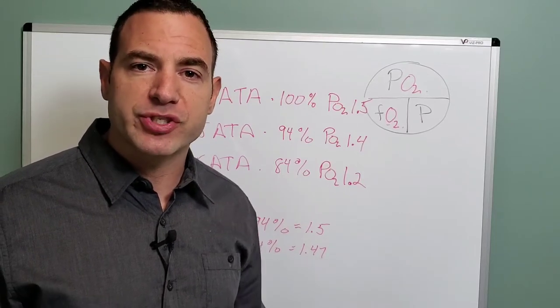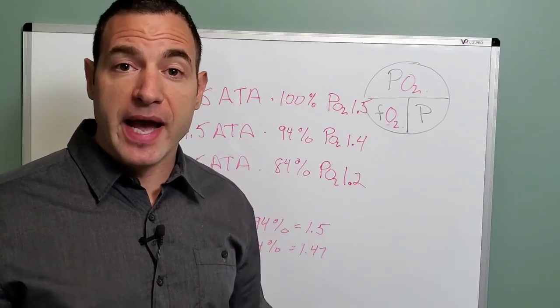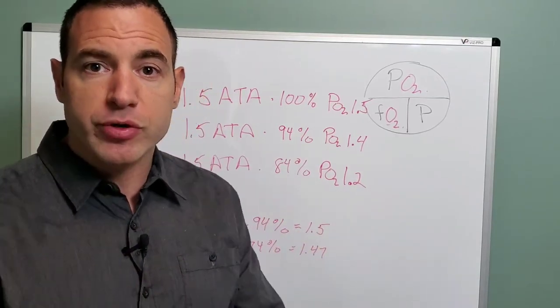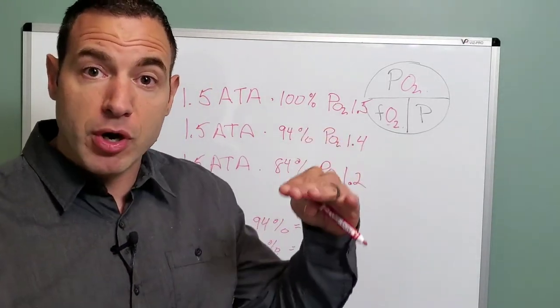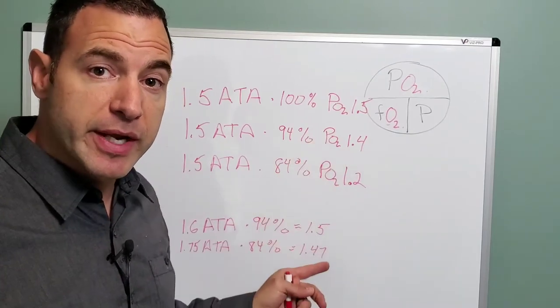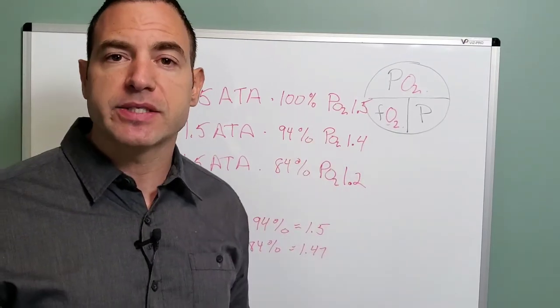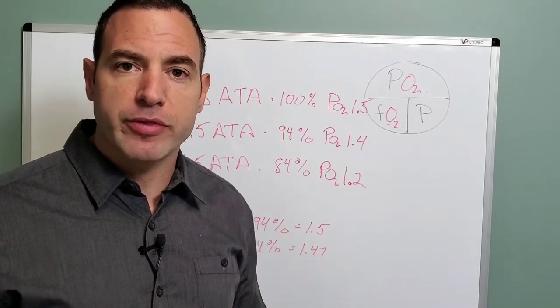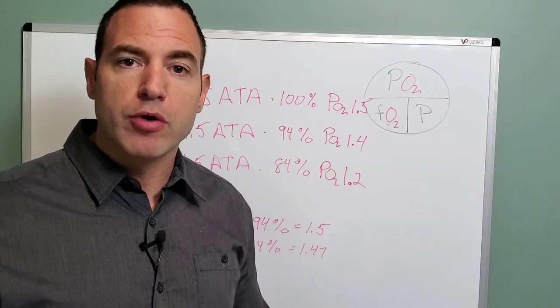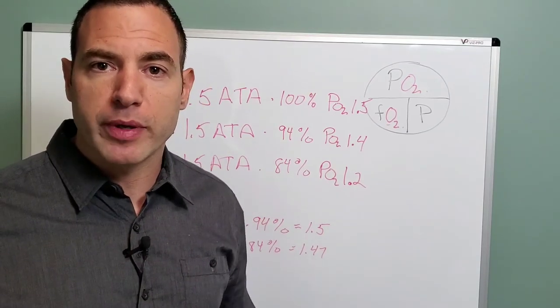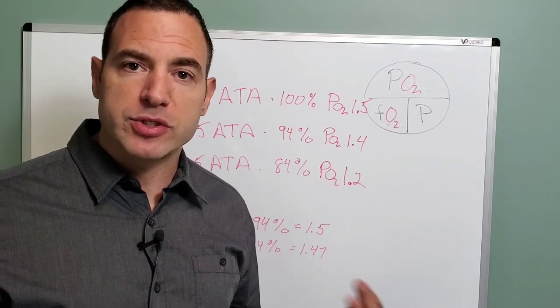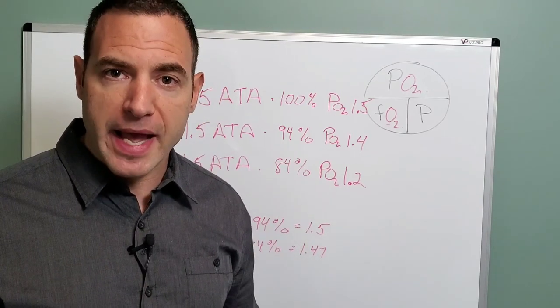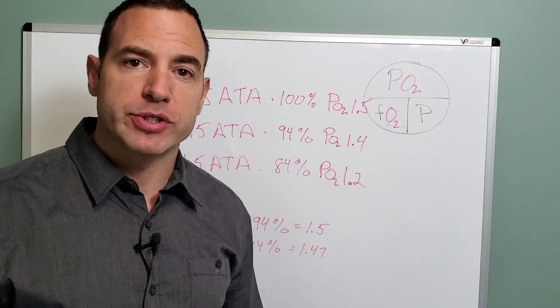So my point is just to show you that if we have the ability to manipulate what the patient's using for breathing, what the internal environment is, what the pressure amounts are, and the percent oxygen that they're getting exposed to, we could very easily create similar environments where we could know that the patient is getting the proper dosage across the board regardless of which equipment, which technician. As long as we're speaking the same language, we could be consistent with the actual dosage and the actual treatment that we want the patient to get.